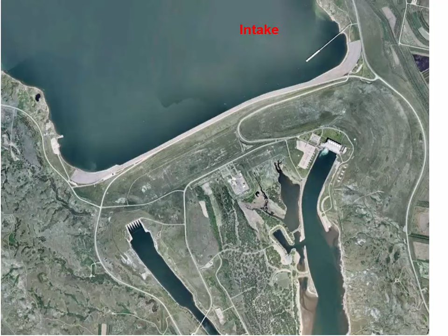Most of the time, I'd say 98% of the time, all of the water that exits the dam goes through the power plant. But when it rains really hard upstream, when there are storm events that make it so that the maximum capacity of this power plant is exceeded, then they'll sometimes send the overflow water through these emergency release gates. And so it's sort of like a medium emergency. It's not an emergency so big that the water's flowing over the top of the dam, but it means that there's a lot more water than ordinarily they can handle through the power plant. So that's what these release gates are here.